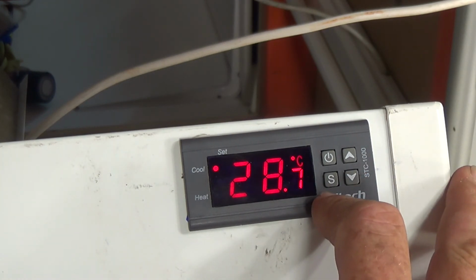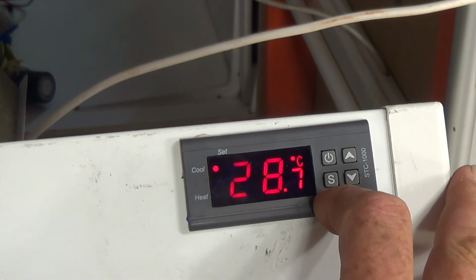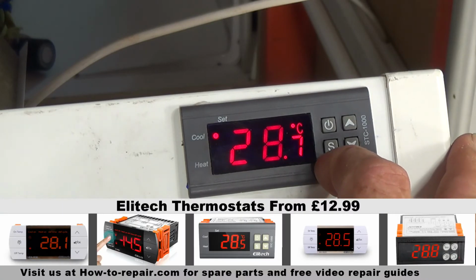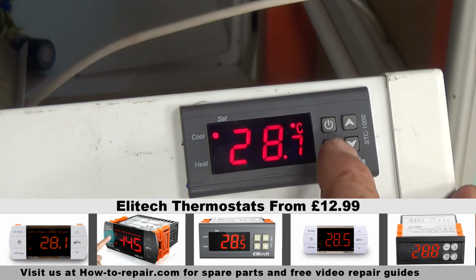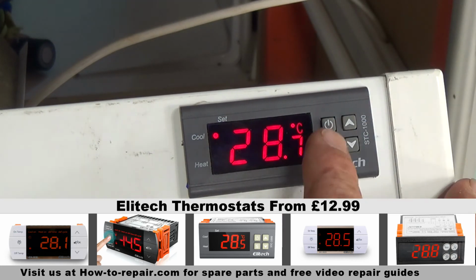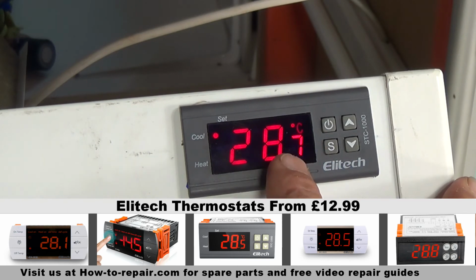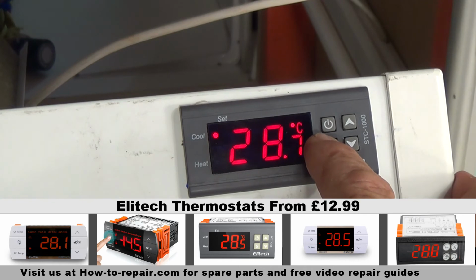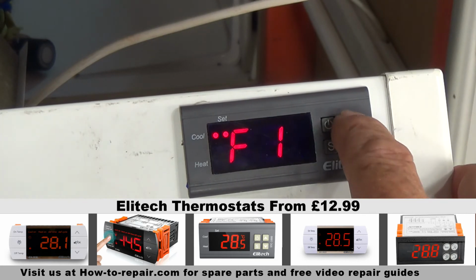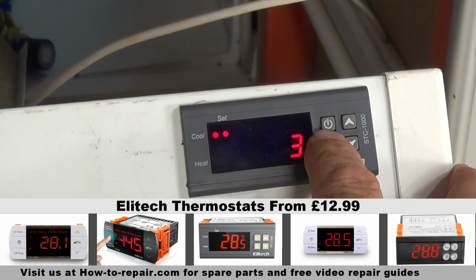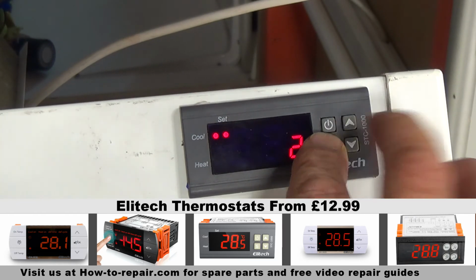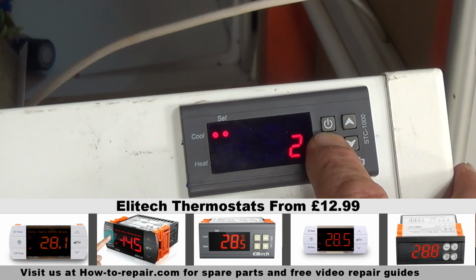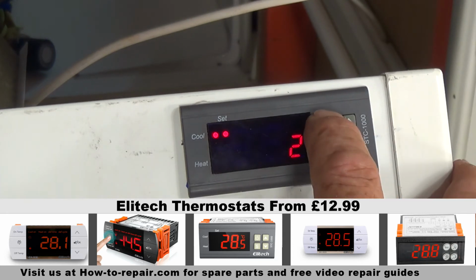The next thing we're going to set is the compressor shut-off time. This means if the power is cut off from the compressor, in other words, we had a power cut or accidentally disconnected the machine, it's how long the delay time to protect the compressor is set. Now we'll just go into set. We can go to F3. It's set at 3 minutes. I'm going to change that to 2 minutes because 2 minutes is fine to let the compressor cool down and lose the pressure before it restarts. Press the on-off button.